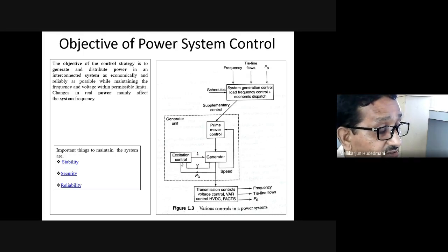As well, the voltage and power output is fed to the excitation system, which will convert these two parameters into field current for the field of the generator so that the terminal voltage is maintained at the stated value. Later, it delivers the power to the grid, wherein transmission control, voltage control, volt ampere reactive control, HVDC, and flexible AC transmission system, etc. will look forward for frequency output, tie-line power flows, power flow out of this generator, etc.